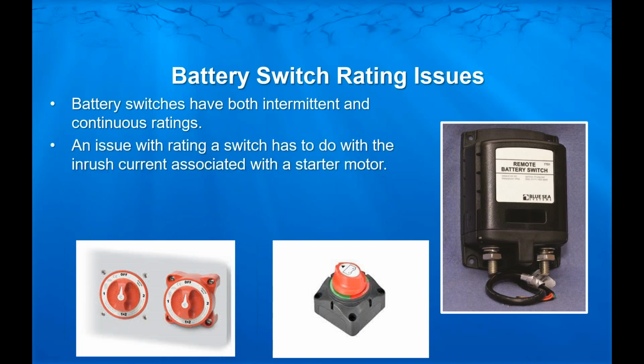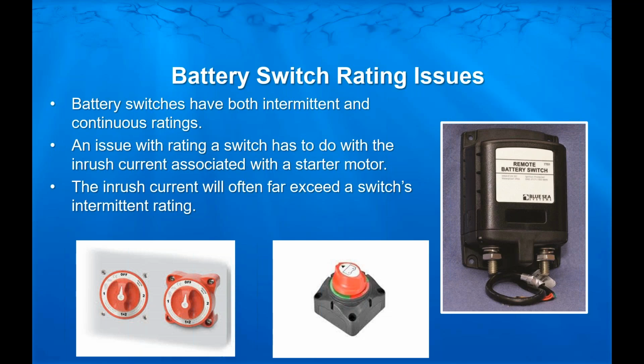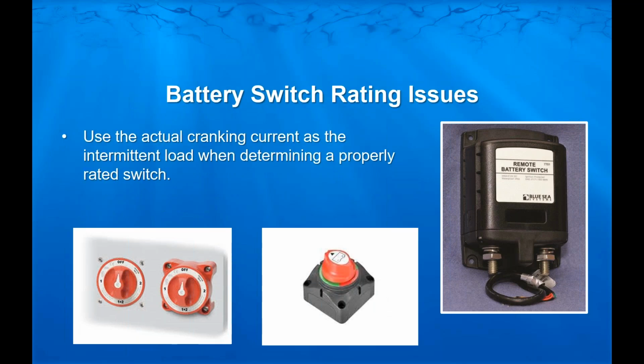So they have intermittent and continuous ratings. The biggest issue with switches is for cranking circuits and the inrush current that is associated with starter motors. The inrush current is going to, more often than not, far exceed the actual switch's intermittent rating. In those cases, you're going to use the actual cranking current as the intermittent load when determining a properly rated switch. That momentary inrush is not enough to damage the switch. But again, as we discussed before, it is enough to blow a fuse. So in this case, we're worried about the actual cranking current. That's the current that may flow for 2, 5, 10 seconds in hard starting circumstances, and that's what we want to rate that switch to.